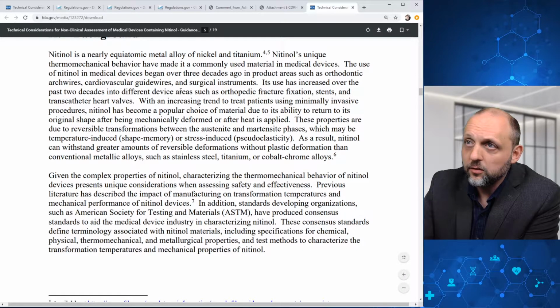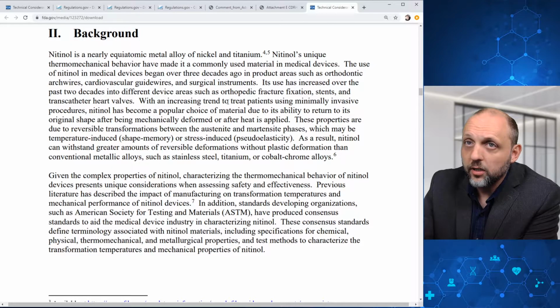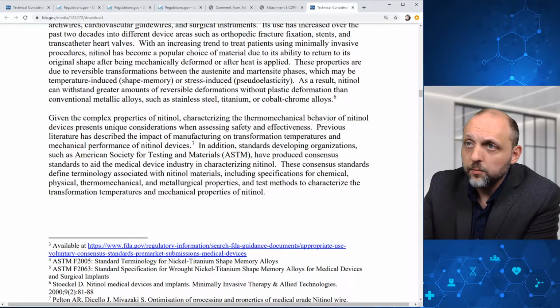Here's some more background on nitinol and its unique properties, and some detail about the use of nitinol over 3 decades in medical devices, in what areas it's primarily been used in. FDA also calls out the increase of use over the past 2 decades into different device areas, and some of the specific mechanical properties. Shape memory, here they call it pseudoelasticity. And given the complex properties of nitinol, characterizing the thermomechanical behavior of nitinol devices presents unique considerations when assessing safety and effectiveness. And here they call out literature, as well as some work done by ASTM, which we'll see later on in this document. And they specifically call out the consensus standards that aid the medical industry in characterizing nitinol.